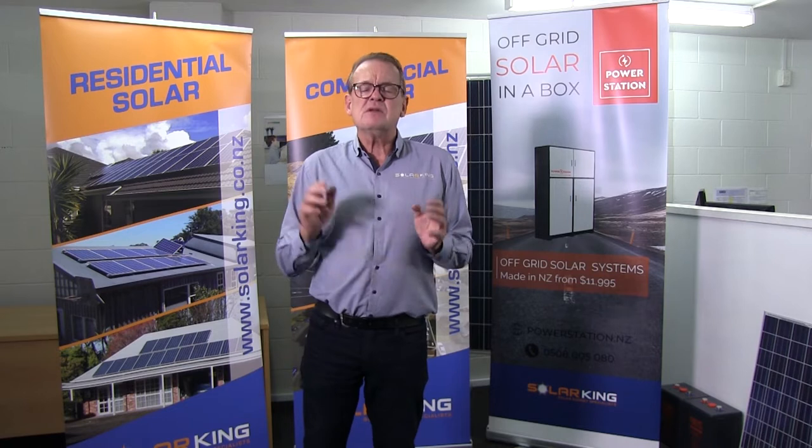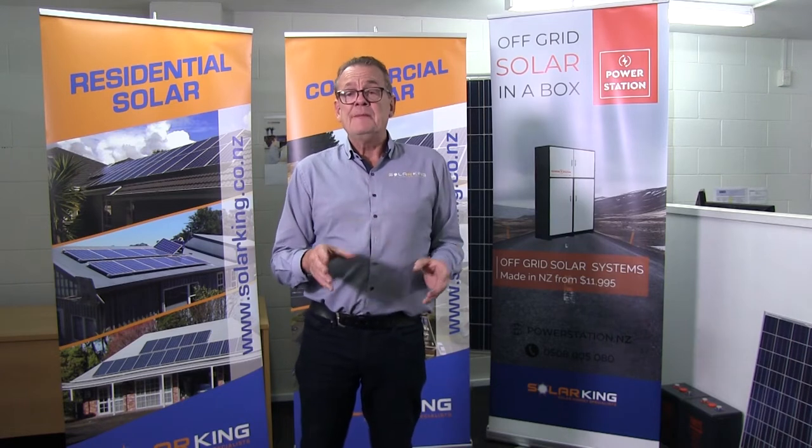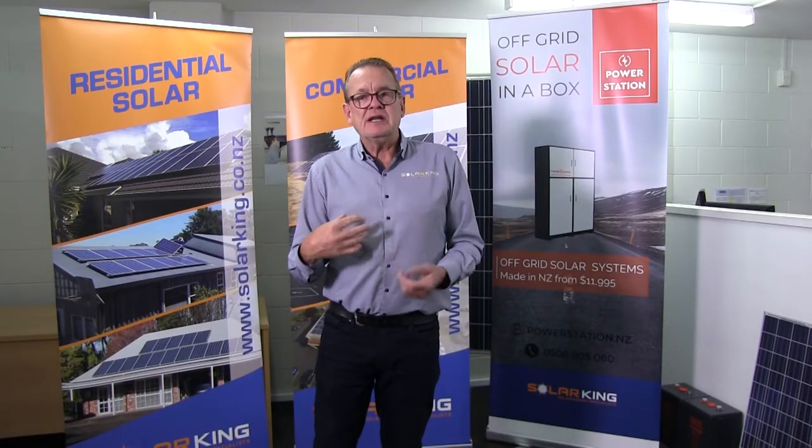There are lots of batteries on the market. We keep hearing about lithium batteries, power walls, and various options. Lithium is definitely a very good battery option, particularly in a hybrid situation where your batteries store the power, you've still got the mains, and the batteries support your mains power overnight or during peak use. There are different lithium technologies — lithium-ion versus lithium ferrophosphate, commonly called LFP. There's been a lot of debate that LFP is the safer lithium, whereas lithium-ion can have issues like thermal runaway, which is an unstable situation.